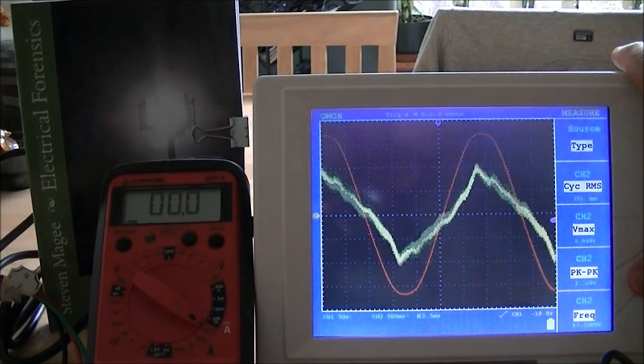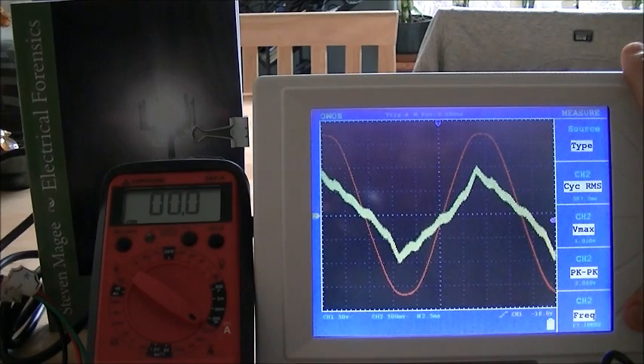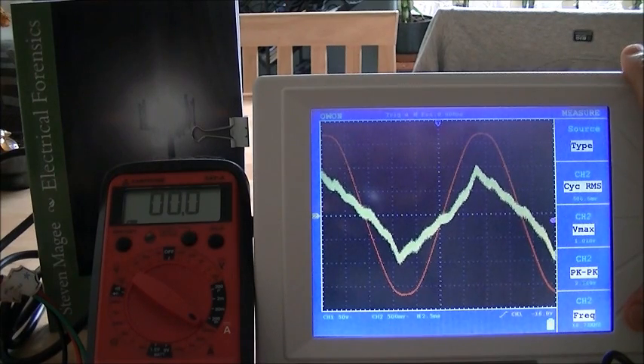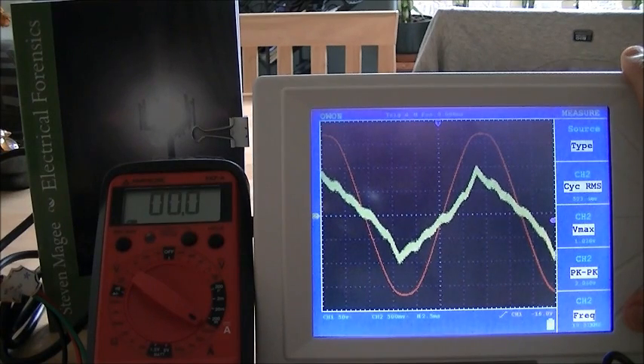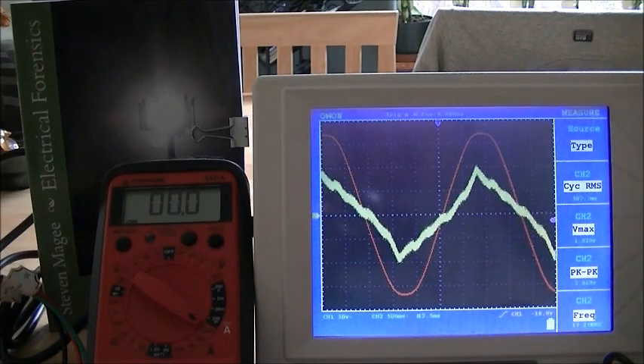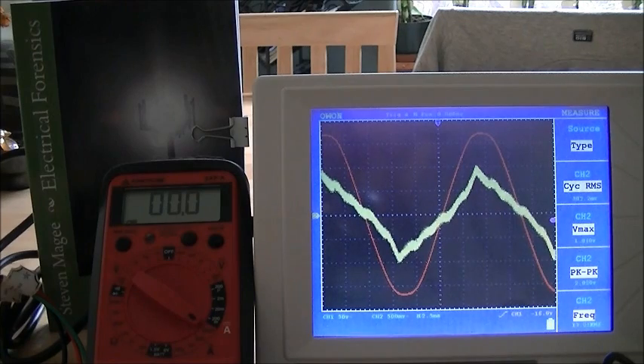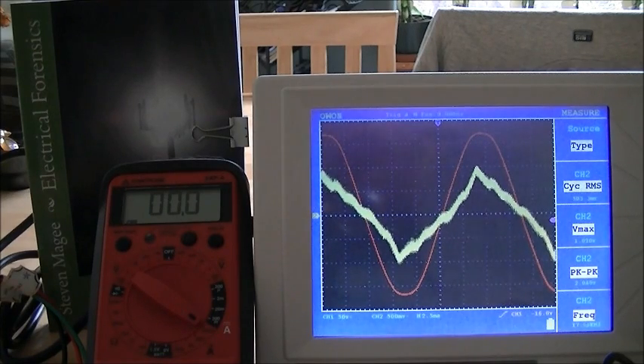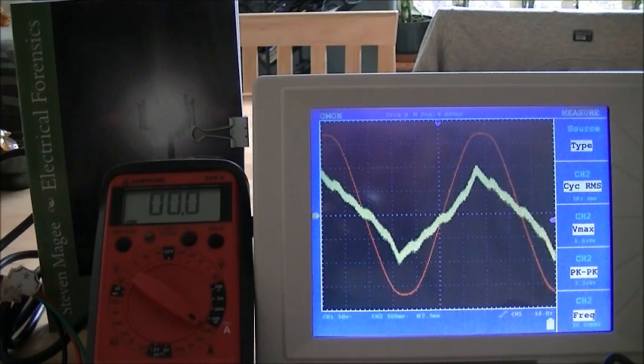We have a frequency which is kind of interesting, about 17 kilohertz. It bounces around a little bit but seems to be between 17 and 19 kilohertz and that's all that junk that you can see making the line thick on the waveform. If you look at the red waveform it's nice and thin but the other waveform is thick and that is an indication that it has a lot of high frequency noise riding on it.